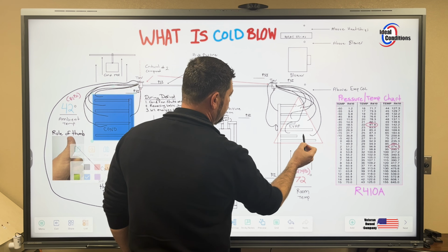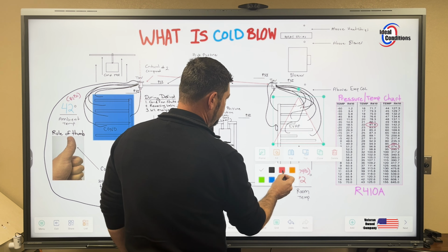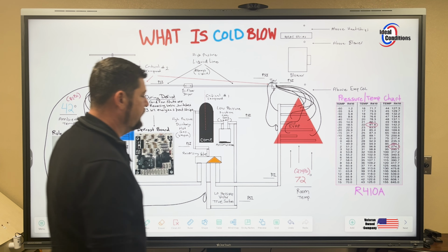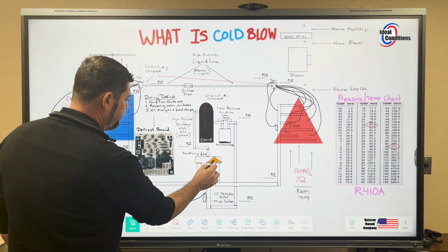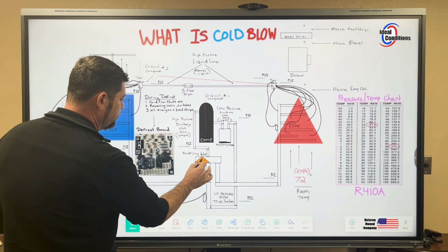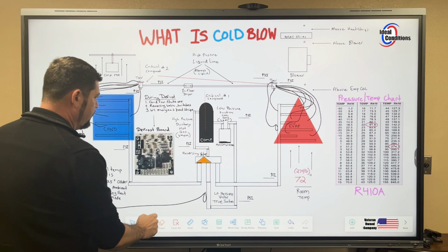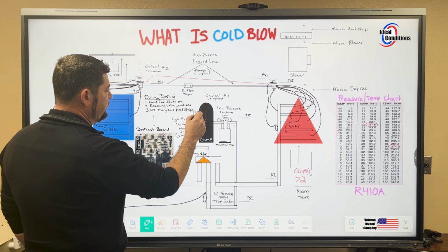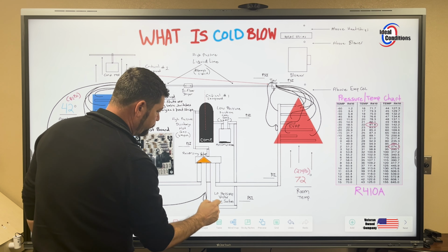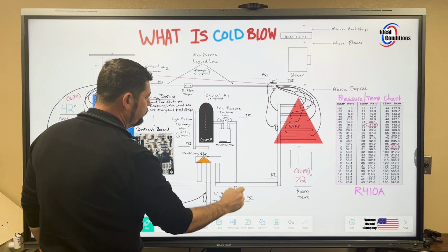We're going to say the air handler is now going to be red because we have hot gas flowing into it. We're going to move our valve over. The valve's in the heat mode position, and hot gas leaves the compressor, flows through the reversing valve and into the evaporator. And so we're going to write some values down, and that should help better express what we're looking for here.